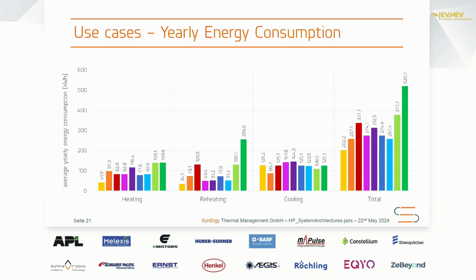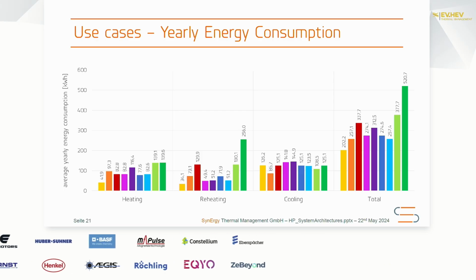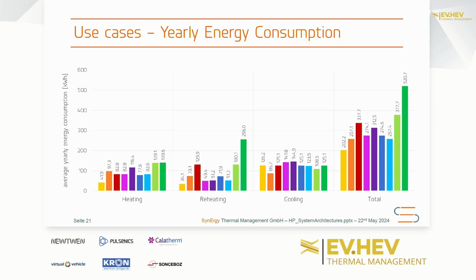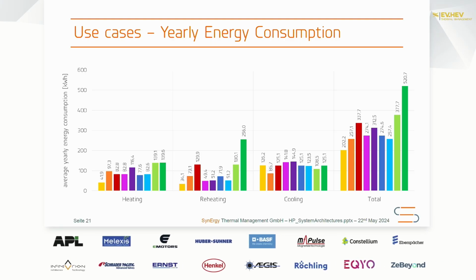There are other systems that are not able to provide the complete heating performance with the heat pump. They're also a bit higher on the level, and a well-designed heat pump system that can operate on different pressure levels and can control them with externally controlled valves is able to provide both the cooling and the heating performance as required without additional heating from the electrical side. And the most right set of columns, that's the total energy consumption over the years. So we see here also some big difference in some heat pump systems that are not able to always operate the heat pump system in the most efficient way, mainly due to the orifices or TXVs, or if they are not able to provide heating performance, that they have to add electrical performance or use a short cycle, which is also less efficient than electrical heating in the end. So that is what leads to these results.